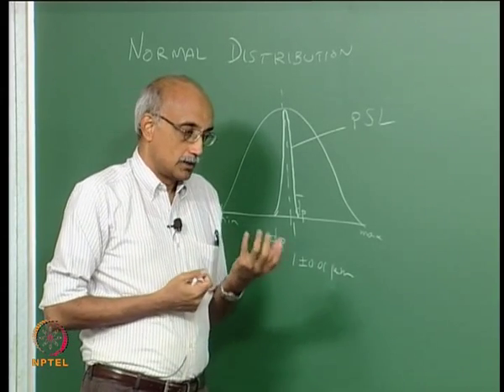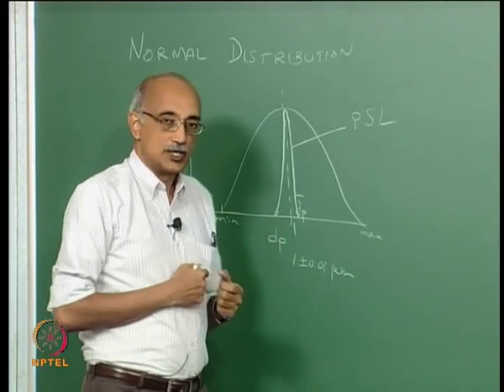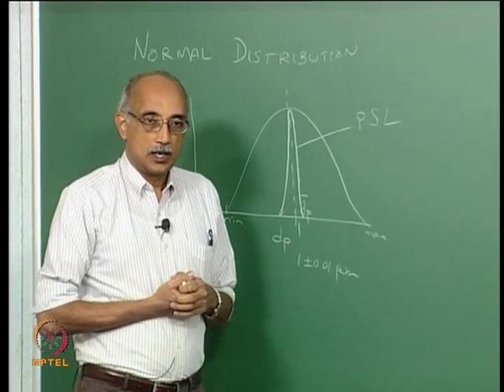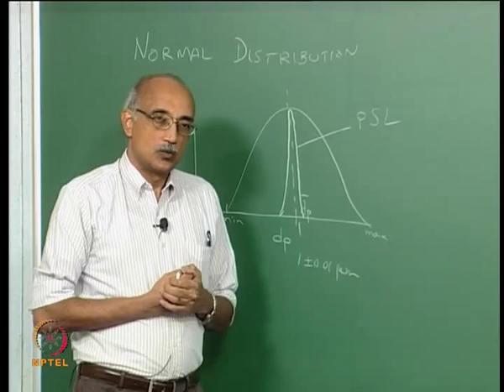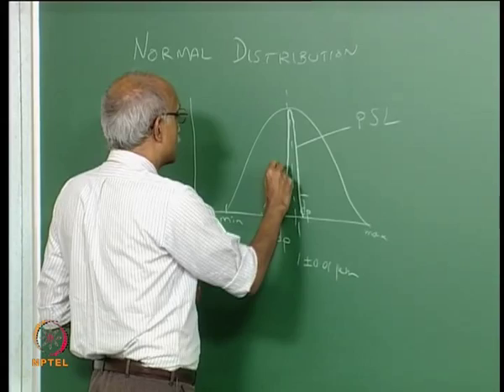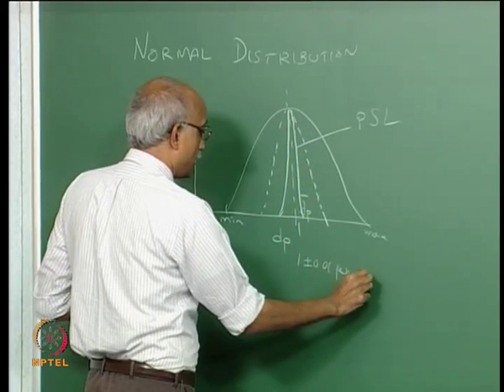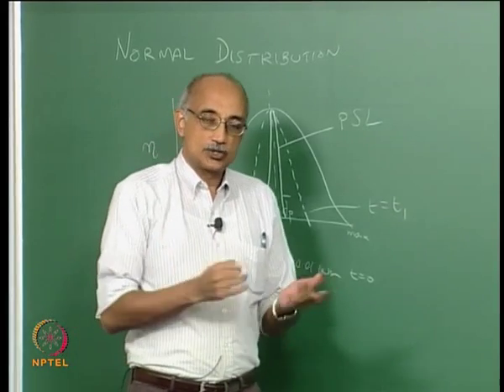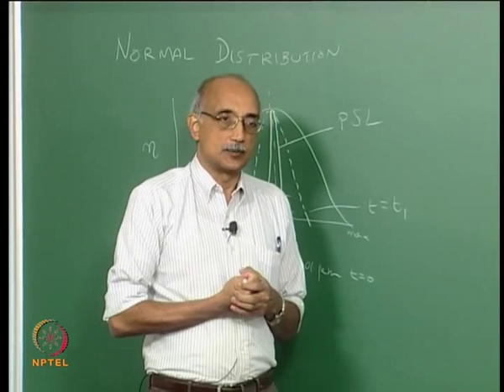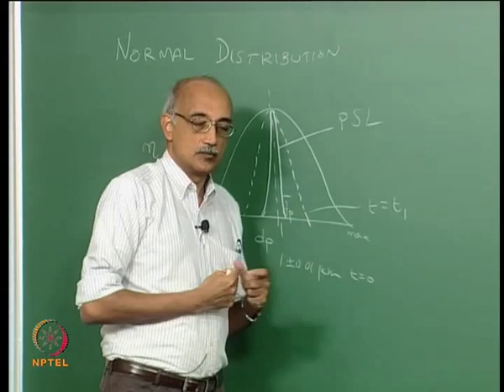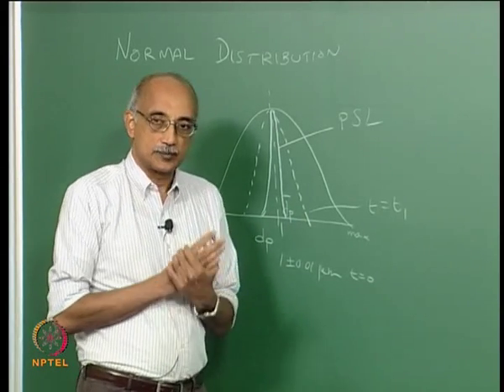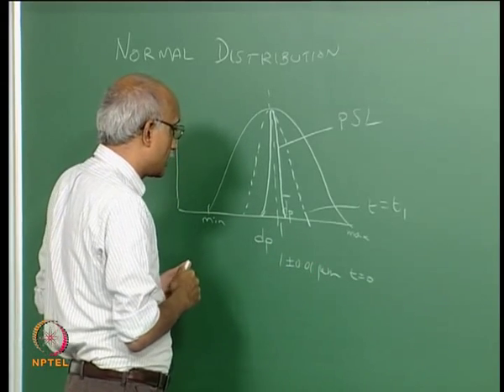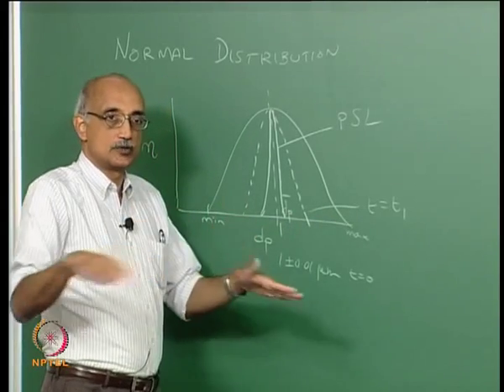If you take a vial or beaker containing these calibration standards and let it sit on the shelf for some period of time, the population will show signs of broadening after a month of shelf storage. At time zero you have a tight distribution, but at time t1 the distribution has broadened. Broadening of the distribution happens because of additive and subtractive effects — you take an initially mono-dispersed population, allow addition and subtraction phenomena to occur, and you start seeing a broadening of the spread. Over a period of months, the distribution will keep getting wider and wider.